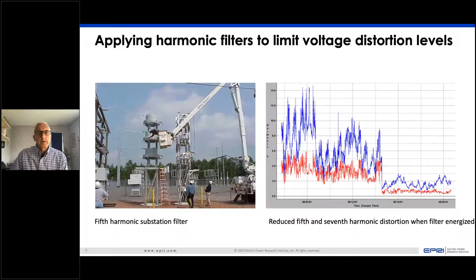So many years of research have gone into this. IEEE standards like 519, and the IEC 61000 series, 61000-3-2 and 4 and 6, all deal with compatibility, starting with making sure we don't inject too many harmonics with nonlinear loads like electric vehicle battery chargers, but also making sure that we don't create resonances that magnify those harmonics. So we've come a long way in harmonic analysis, but it's still an area of ongoing research.